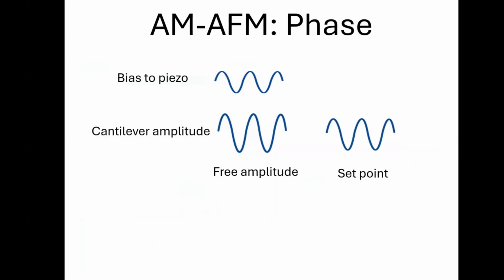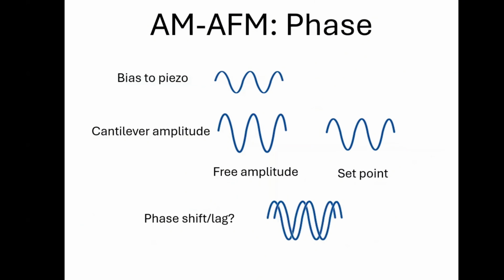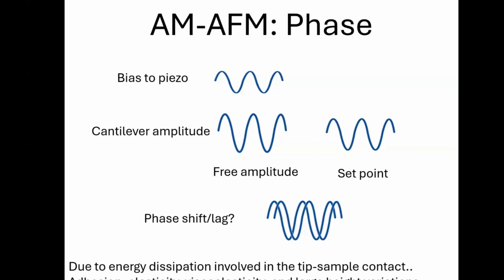Earlier, I mentioned phase, so let's revisit that. What happens when the tip taps the surface? Something different must happen if the sample is hard or soft. This can be apparent in the phase signal, the phase shift or lag between the drive, the AC voltage we send, and the response that we measure. The tip will bounce back immediately from a hard surface, but lose energy in tapping a soft surface. While it would be nice to just attribute it to hard versus soft, it can be more accurately described by energy dissipation in the tip-sample contact, and it can relate to elasticity, but also surface chemistry and topography.